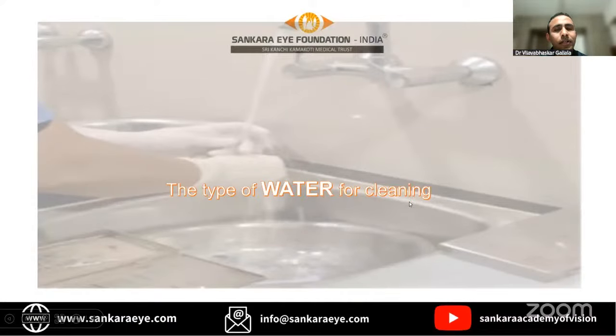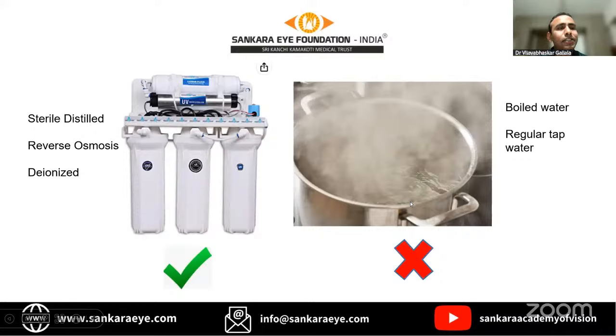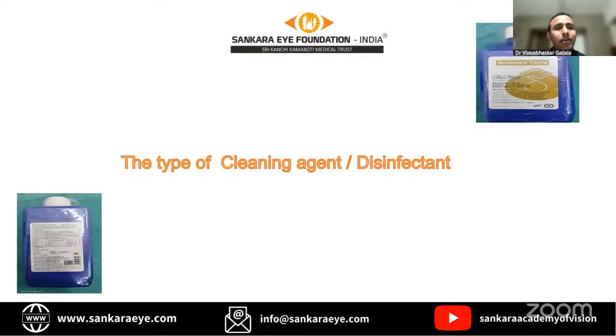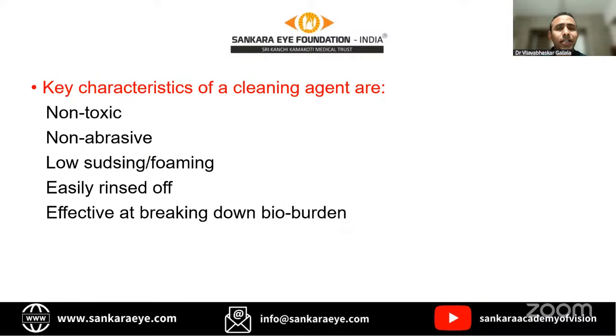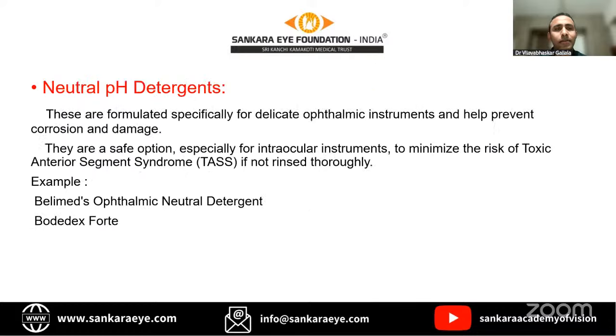So what type of water should we use for the cleaning? Critically, sterile distilled water, reverse osmosis, or deionized water, you can choose anything, but try to avoid boiling and running water. Of course, we are not using them nowadays, but still we should remember that. And what type of cleaning agent or disinfectant should we use to clean the ophthalmic instrument? For the initial cleaning, the cleaning agent should be non-toxic, non-abrasive. It creates low foam and is easily rinsed off, and it is effective at breaking down bioburden.